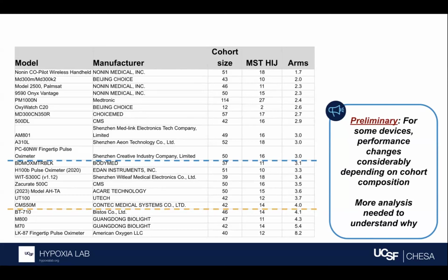One thing that I want to draw attention to that's not visually shown here: if we compare the result, the ARMS, this error, when we had the cohort size of 10 for the same device, to now when we have a larger cohort size and a more diverse cohort, for some of the devices it hasn't changed that much. We get a similar finding. But for other devices, it has changed them from being clearly not passing to passing, or clearly passing to not passing.